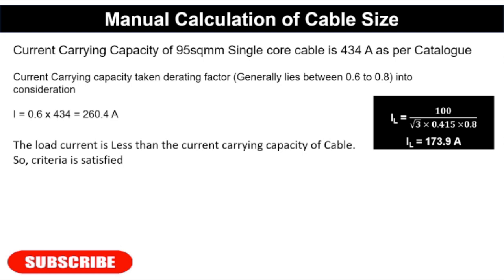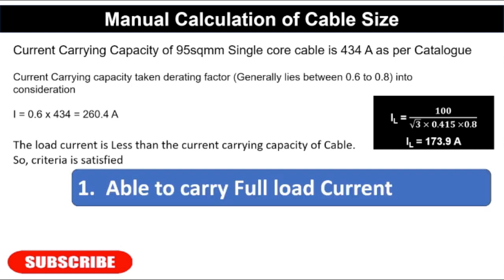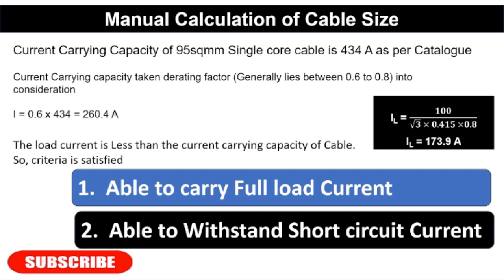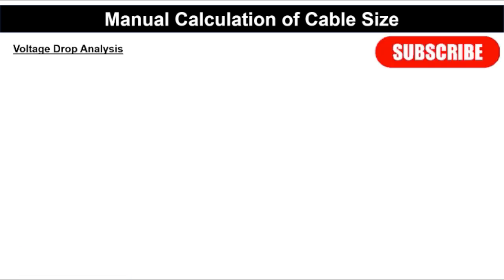So two criteria are now satisfied. First, the cable is able to carry the full load current — the cable has a current rating of 260.4 amperes and our load current is 173.9 amperes. Second, the short circuit current criterion is also satisfied, as the 95 mm² cable withstands 9 kilo-amperes. Now we check whether the voltage drop criterion is satisfied.